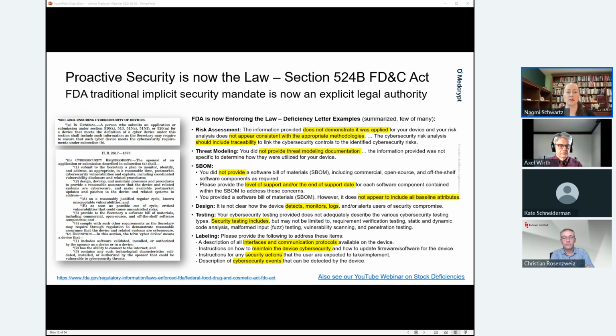this information. They can ask very specifically for plans to monitor in the post-market. They can ask very specifically for a detailed description of the processes and procedures that will provide assurance of security of these medical devices. And they can ask, and they will ask, for a software bill of materials. Now that is provided to the secretary, in other words, to FDA. It does not necessarily mean that you have to provide it to the public. But what you see in the way that the statute was written is that FDA is saying, we do not want to argue with manufacturers anymore about whether or not the risk management aspects apply. They do. Here's what we want to do about it.